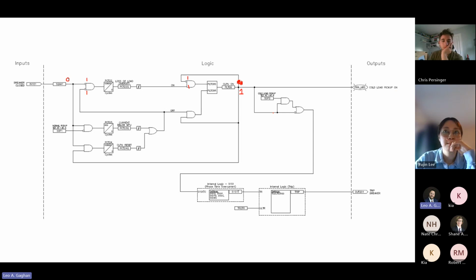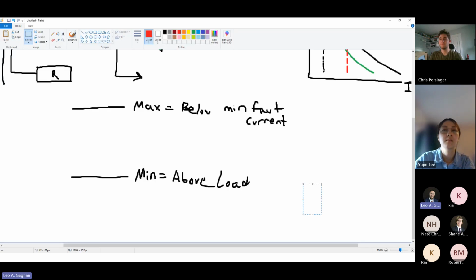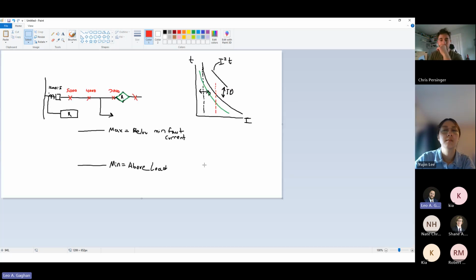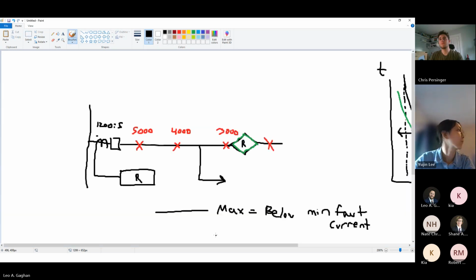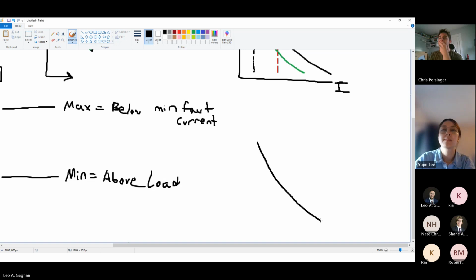So we've got this 1 coming in. So now what happens is we've got a 1 here, which means we got a 0 there, but that's not going to pass through. We need the current to be above 1.9 amps in order to get a 1 here. If that current is above 1.9 amps, then our torque control will be a 1 and our element will be allowed to operate. So what ends up happening there is we've got our normal pickup of 1.4.